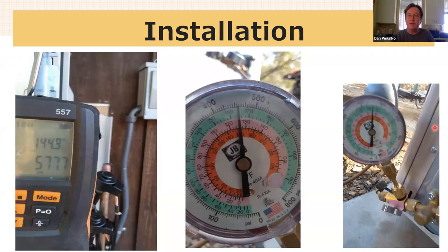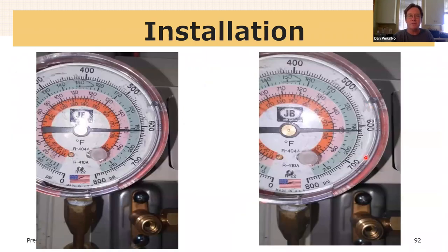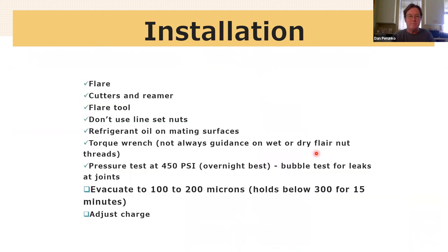This is measuring nitrogen, right? This is a little tiny analog gauge. This is a digital gauge and you can see it's 577 PSI there. And 455 PSI in that one. And this one is over 550. So just different tests. Here's some tests at 600. And that just depends on the manufacturer, right? Fujitsu says 600, other people say 450.